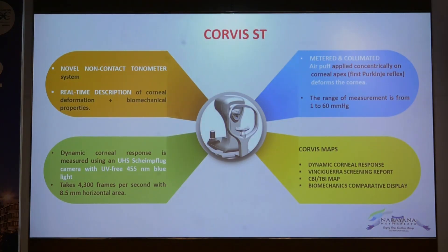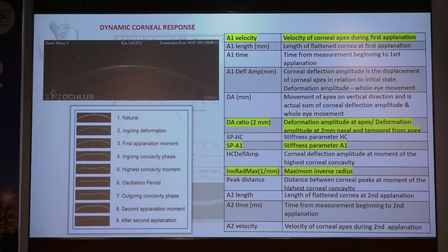Coming to the corneal biomechanics — the Corvis ST is a non-contact tonometer that gives a real-time description of corneal deformation and biomechanical properties. It has a Scheimpflug camera with UV-free 455 nm blue light, gives 4300 frames per second, and delivers a metered collimated air puff that deforms the cornea, with a measurement range of 1–60 mmHg. The Corvis maps include the dynamic corneal response, the Vinciguerra screening report, the CBI-TBI map, and the biomechanics comparative display. In the dynamic corneal response, which has 9 stages, the most important parameters are the A1 velocity, the DA ratio, the SP-A1 or stiffness parameter, and the inverse radius max.